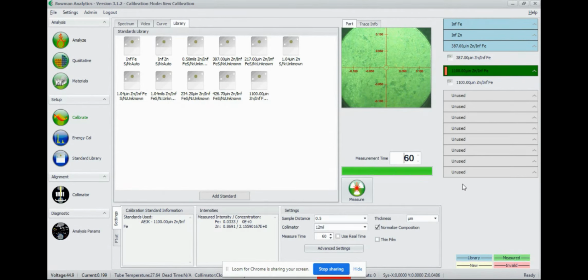So we have all of our standards in place now, and we're going to say that this is enough because we've only got a single layer. So what we'll do with this application is we've got our low standard 387 and our high 1100, and we'll verify that with some standard in between when we actually build out the application. If we had multiple layers, multiple elements, alloys, things like that, we're going to want more standards to account for those different layers.